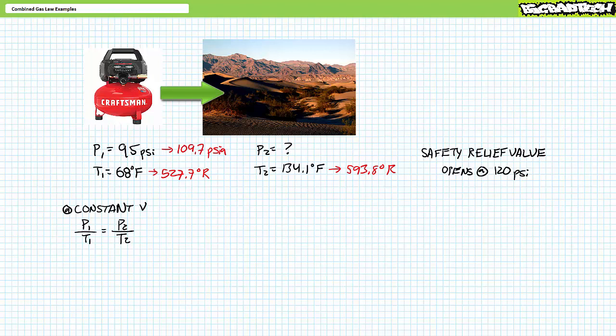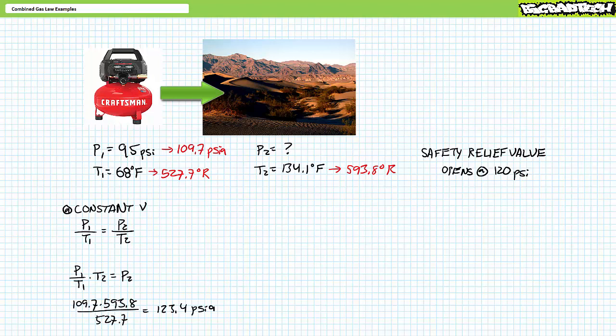We know P1, T1, and T2; we want to determine unknown pressure P2. An algebraic manipulation of Guy-Lussac's law gives P2 equals P1 times T2 over T1. Substituting in the given values, P2 is found to be roughly 123.4 psi absolute. You need to convert this back to the gauge scale — 123.4 psi absolute is roughly equivalent to 108.7 psi gauge. The safety pressure relief valve stays closed.